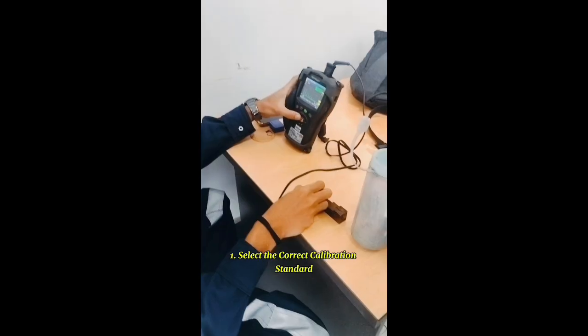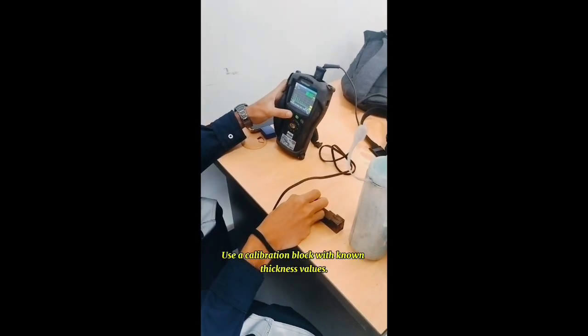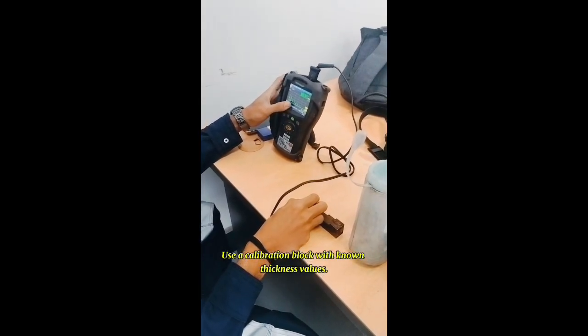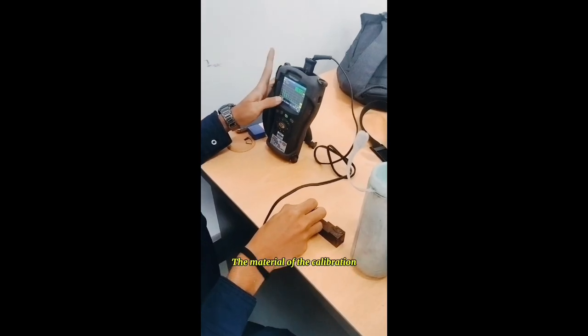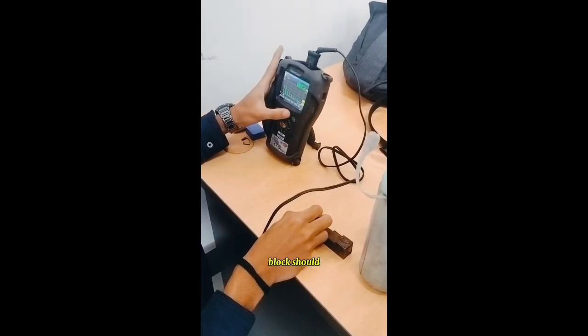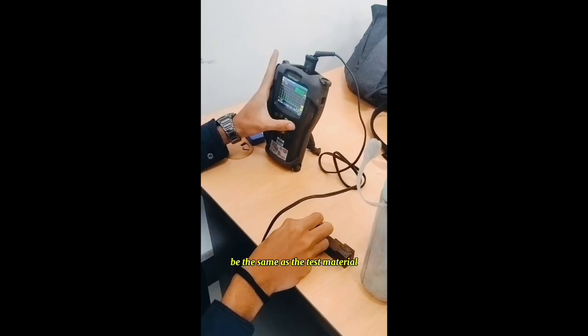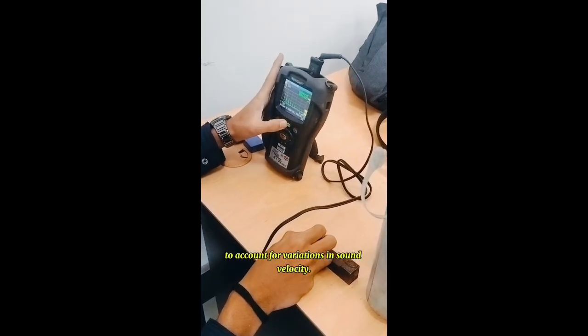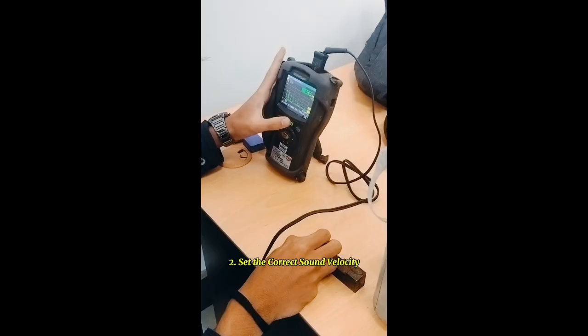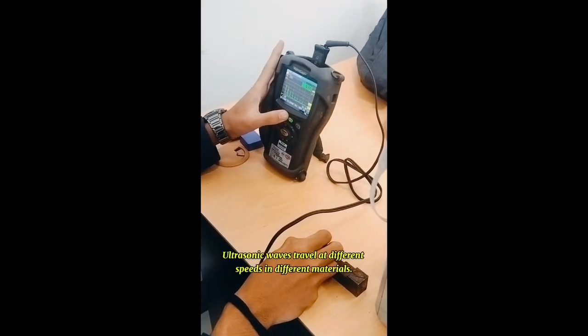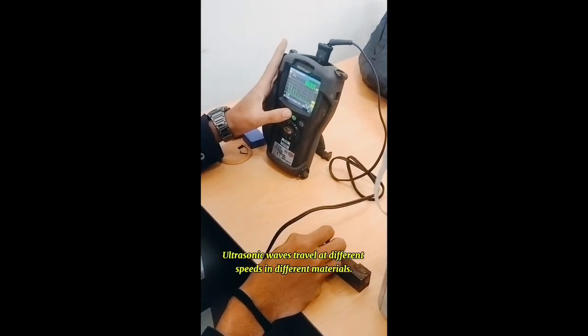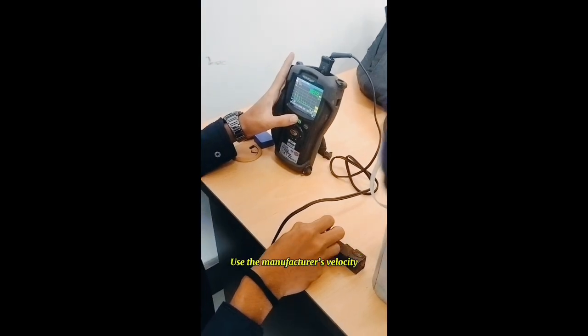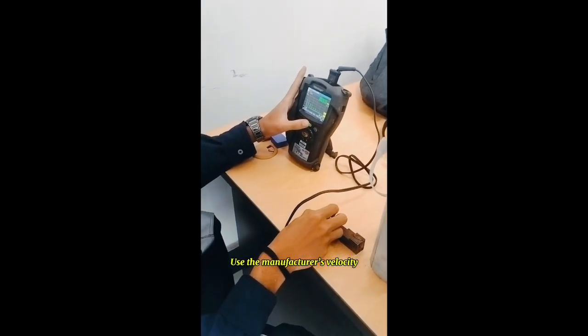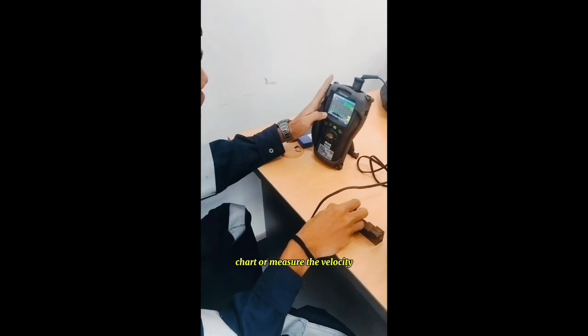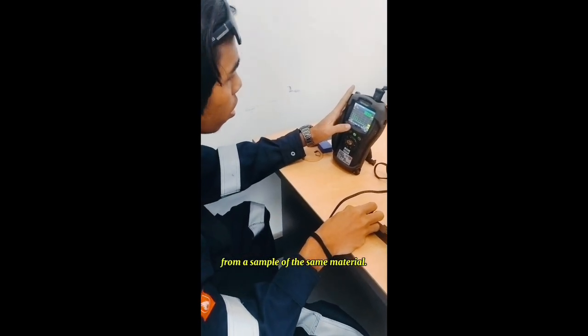1. Select the correct calibration standard. Use a calibration block with known thickness values. The material of the calibration block should be the same as the test material to account for variations in sound velocity. 2. Set the correct sound velocity. Ultrasonic waves travel at different speeds in different materials. Use the manufacturer's velocity chart or measure the velocity from a sample of the same material.